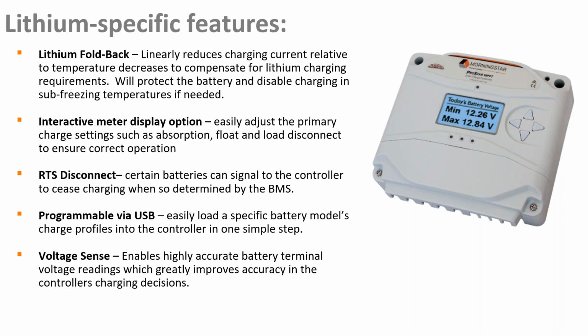Also, among some other sophisticated features, the remote temperature sensor can actually double as a sort of auxiliary disconnect or a remote on-off switch. So certain batteries, if they have additional output signaling on their battery management system, can use that to open or close a circuit connected to our RTS terminals for our remote temperature sensor. You typically don't need the remote temperature sensor for lithium battery charging, at least not for temperature compensation, because lithium batteries don't need to be temperature compensated. They're stable throughout the temperature range.